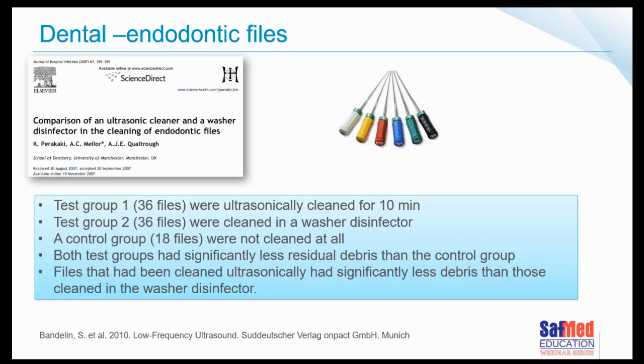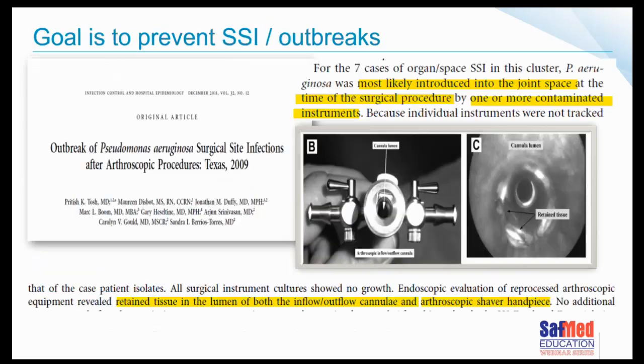Both test groups had significantly less residual debris on them than the control group, but they found in their research that files that had been cleaned ultrasonically had far less debris on them than the ones cleaned in the washer disinfector. So again, different devices are designed for certain purposes. An ultrasonic cleaner cleans these kinds of things better than a washer disinfector does. Important to know.